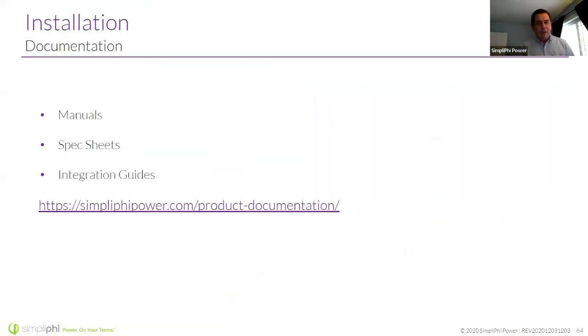Real quick on installation, read the manual. We also have spec sheets and integration guides on our site. And integration guides are going to walk you through a specific inverter or charge controller's set points, and then our recommendations on those set points. So it's really intuitive to use. It's going to give you those set points as they come out of the equipment you're programming on. So, if it's called low voltage cutout or low battery cutout, we're going to be treating those set points the same way the inverter or charge controller manufacturer treats them.